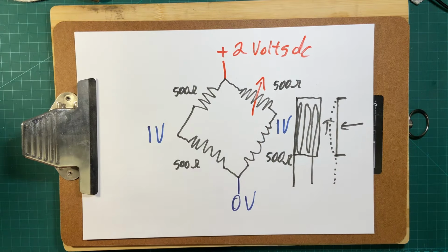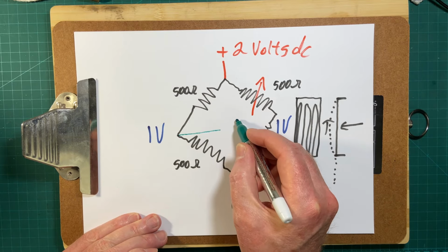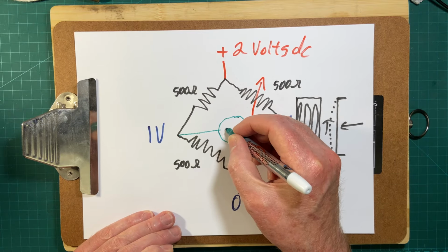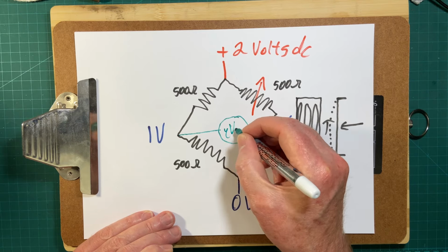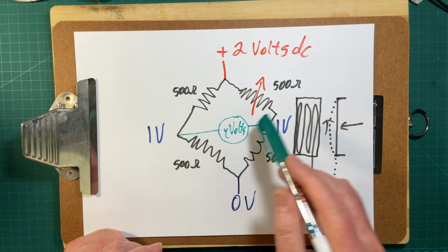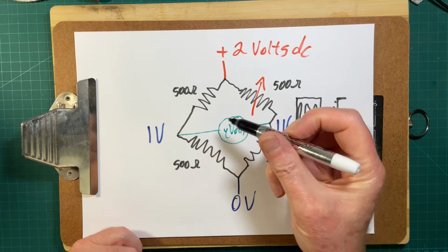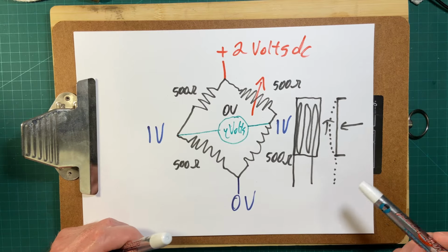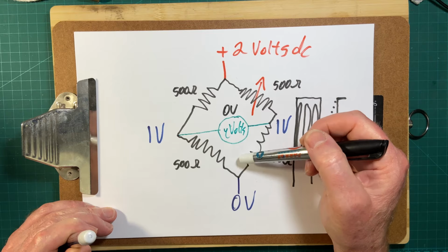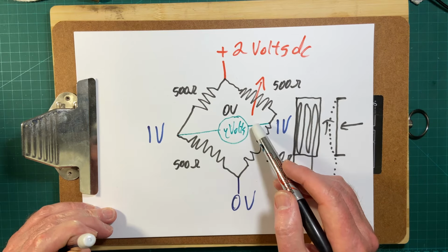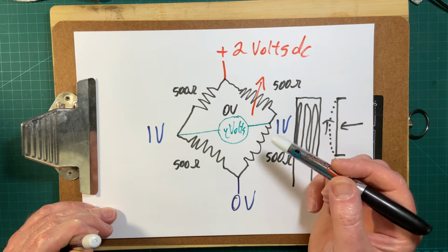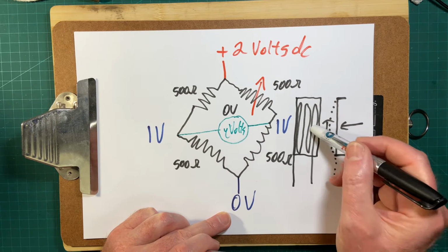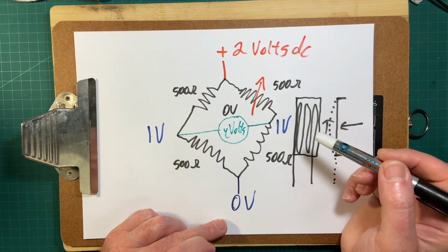So if you have, now, that would be microvolts that this is measured in. So you'd at this stage have 0 volts with no force on that wheatstone bridge. Okay, now this excitation voltage gives you a microvolt per kilogram per volt of excitation. There's a ratio. So the higher your excitation voltage, the higher this potential difference in relation to each kilogram put on here will be. So that's how that formula works.